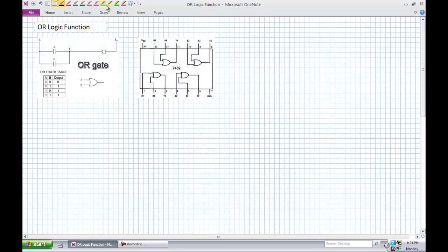So how is the OR logic function applied? You should be familiar with this diagram for motor controls. Like I said in a previous lecture, essential. This is what the digital electronics is doing. It's preparing you to understand the logical control of systems via motor control and PLCs. Whereas an AND was a series relationship with switches, an OR is a parallel relationship with switches. If we look at our motor control diagram up there, if switch A closes, that coil is energized. If switch B closes, that coil is energized. If neither of them close, it is not energized. If both of them close, it is energized. So it's neat. An OR operation can be used as perhaps controlling a piece of equipment from two locations: the A side of the wall, or the B side of the wall, or both together. So it's a parallel operation, OR.